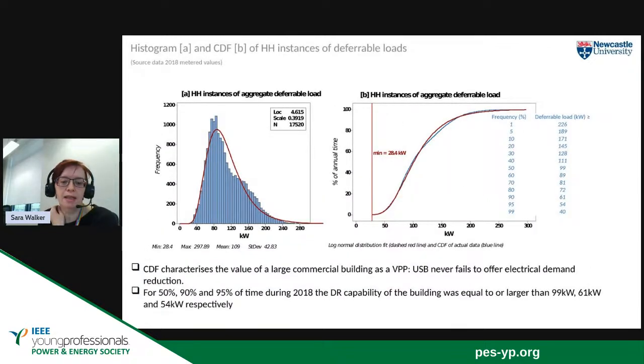So what that means is that there is always some load that the building can defer. We can always offer some demand response. And then depending upon the time of day and the time of year, we can offer more. So if you wanted to be able to offer demand response for half of the year, then the amount of load we could defer would be a minimum of 99 kilowatt.